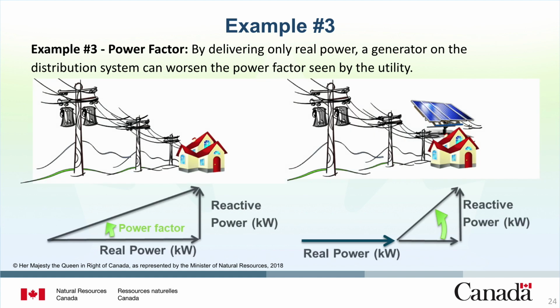The utility generally provides customers with both real power and reactive power. The cosine of the angle between the two is the power factor. However, an interconnected generator only adds real power back to the distribution system, a fact that worsens the power factor. As a result, the utility must generate additional reactive power. However, this can be wasteful and problematic. Should the power factor be much different than 1, the utility will impose charges to offset potential problems.